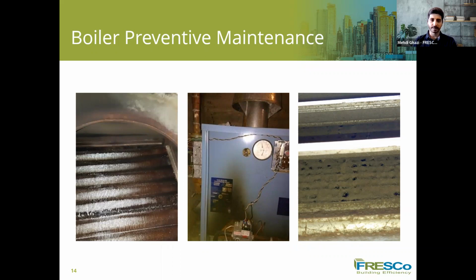Another place in our building that is very important to have on our preventive maintenance plan is our boiler rooms. As you can see in the photos, the boiler rooms sometimes are not in good condition. In the left photo, you can see a clogged heat exchanger surface. It could be solid residue from flue gas condensate, which causes corrosion and clogs the heat exchanger. This can limit the airflow in the boiler and could also cause flame rollout, which you can see in the middle photo, a sign of flame rollout, which can significantly reduce the heat transfer to the water and also increase the temperature of the heat exchanger, and that can lead to a leak from the heat exchanger.